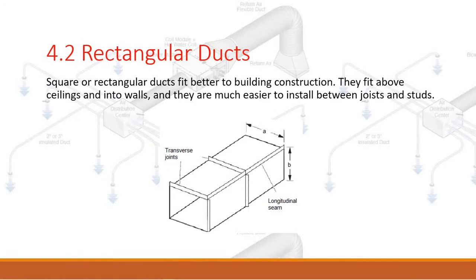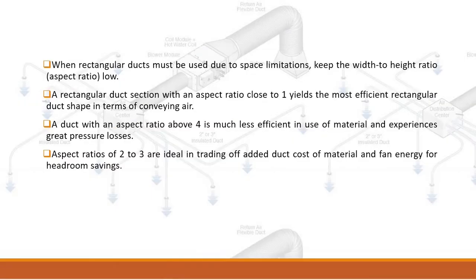Rectangular ducts. Square or rectangular ducts fit better to building construction — they fit above ceilings and into walls, and are much easier to install between joists and studs. When rectangular ducts must be used due to space limitations, keep the width-to-height aspect ratio low. A rectangular duct with an aspect ratio close to 1 yields the most efficient shape. A duct with an aspect ratio above 4 is much less efficient in use of material and experiences greater pressure losses.